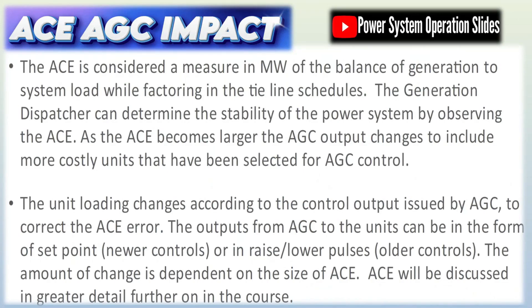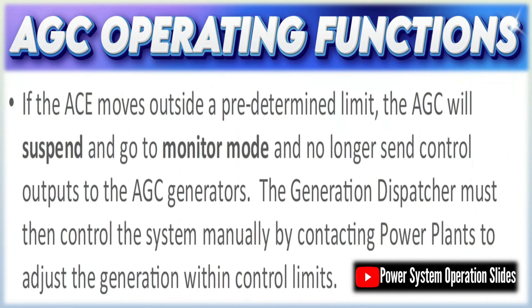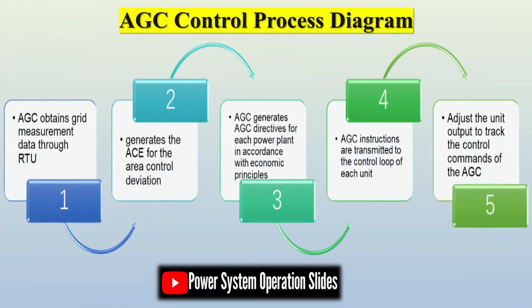The system accomplishes this through a closed-loop feedback process where measurements of frequency, power flows, and generation outputs are continuously compared with set points, and corrective signals are automatically dispatched to the generators. AGC — automatic generation control — is an integrated, computer-based system that adjusts the power outputs of generators in multiple plants if needed to ensure that the total generation matches the instantaneous demand. By doing so, AGC maintains overall system stability and minimizes deviations in both frequency and scheduled power interchanges. Area control error, A.C.E., is the key error signal in AGC.